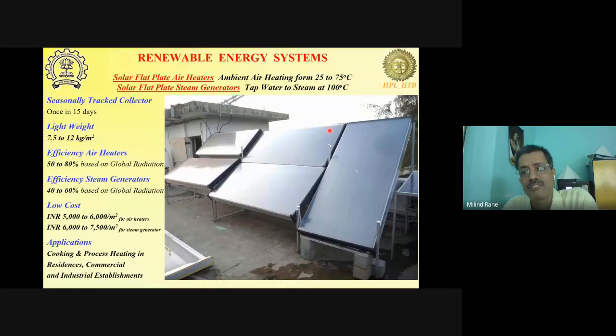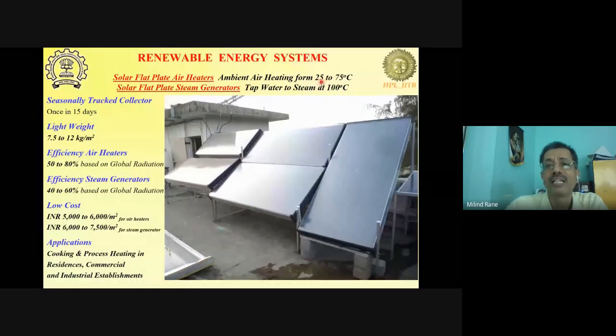The latest technologies that we have to offer on the renewable side are ambient air heaters from 25 to 75. So they look just like simple solar collectors. Okay. And these can be used as a roof of a structure. In fact, we have some photographs in Nagaland. We have deployed 27 of these collectors of 2.1 meters square each as the roof of the agro processing facility there. And then the hot air being drawn from this is used for drying of the agro produce. So once through drying, heating of air from 25 to 75 is easily possible in this.